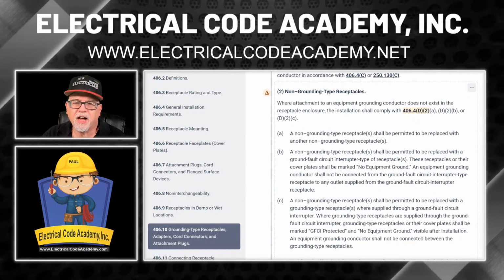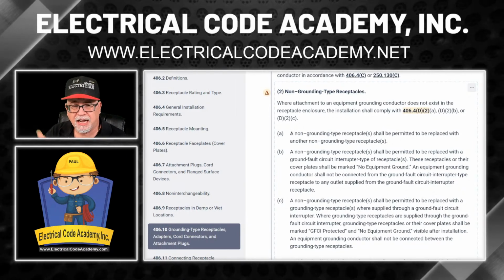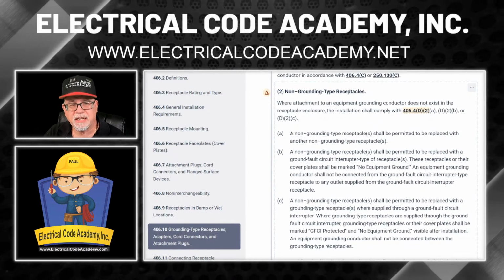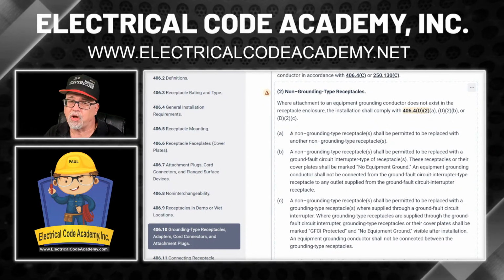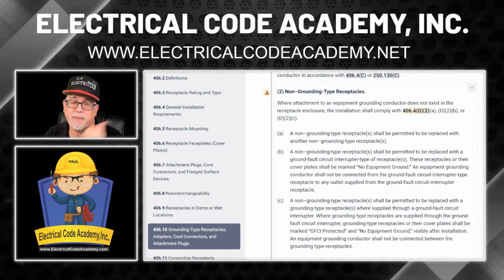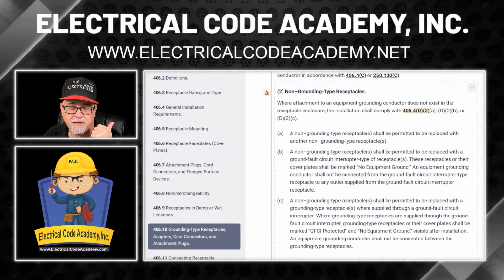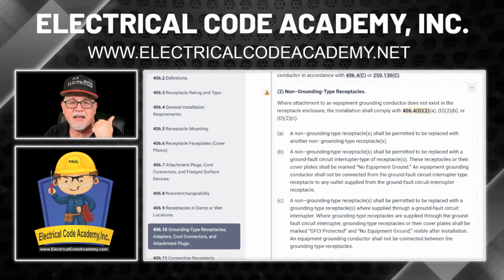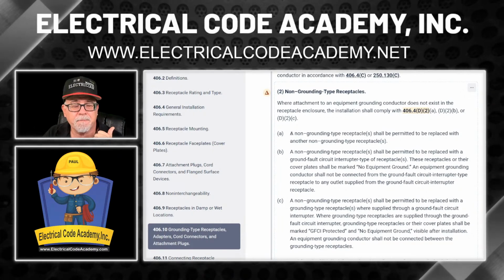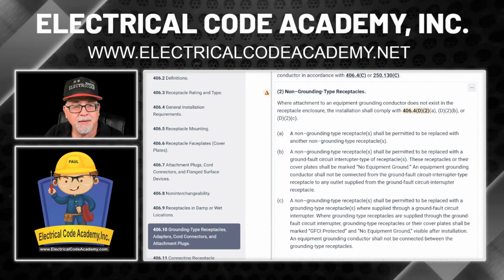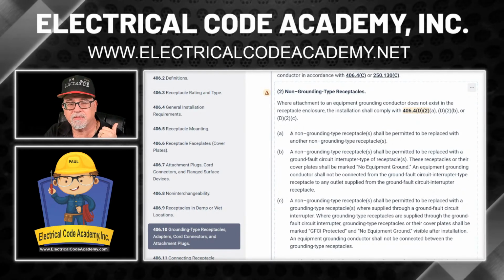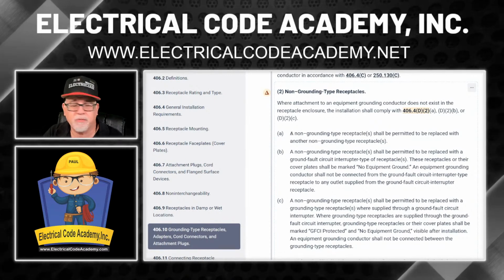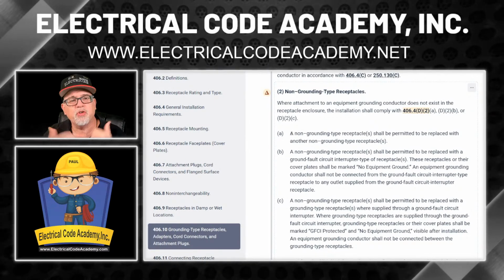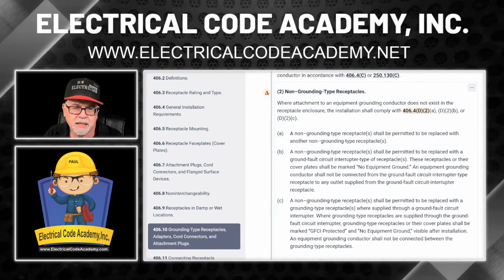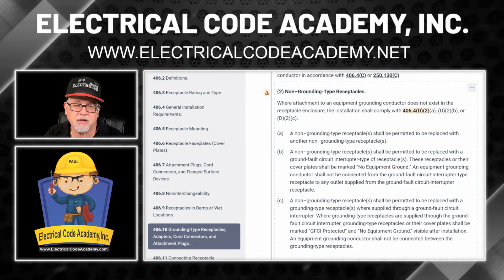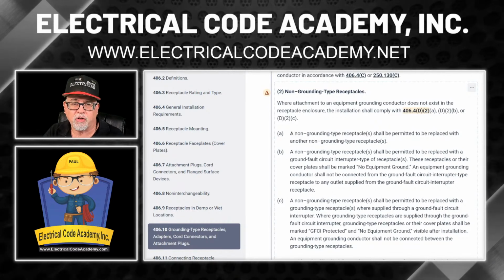Now, one of the other options that you have here is item C. And that is, you could have installed, like we said earlier, the GFCI circuit breaker if the panel can accept one. Okay, so maybe you had an upgrade. And then all receptacles downstream from that are considered protected by the GFCI feature, right? There is still no equipment ground. There is no effective ground fault current path, but you do have this level of leakage current protection afforded you by the GFCI device. It's better than nothing, okay? So that's what you're doing here.